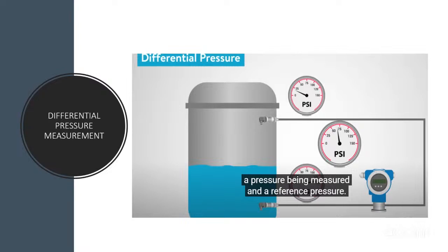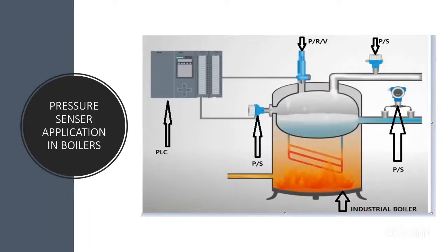In the advanced manufacturing industry, we can also look at the uses of these measurements. That takes us to the next slide, where we have the application in a boiler, for example. Here you can see a picture indicating a boiler. A boiler is used widely in industry to provide steam to destination machines. In this case, we can use this pressure sensor in various ways. For example, you can see here we have PS1, where we are indicating the boiler directly just to observe and view the pressure that is in the boiler itself.